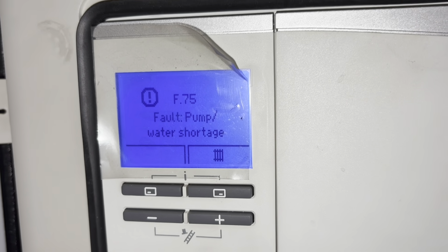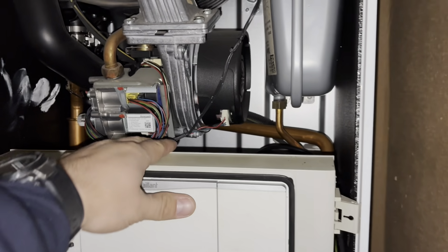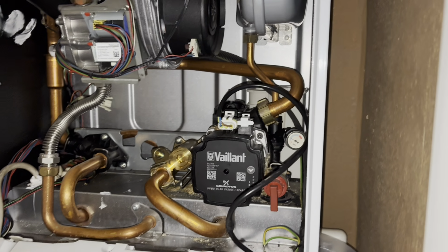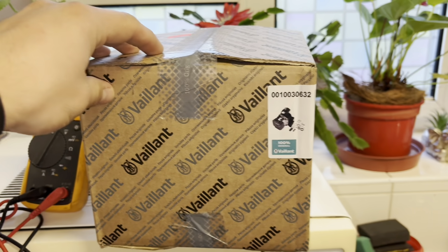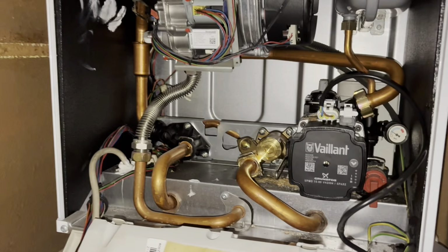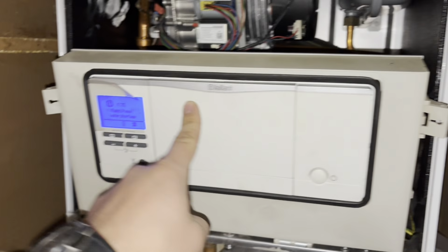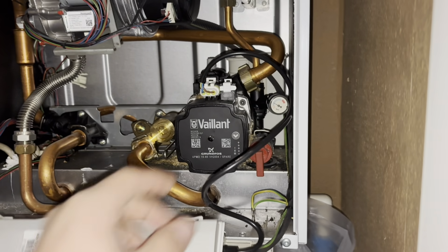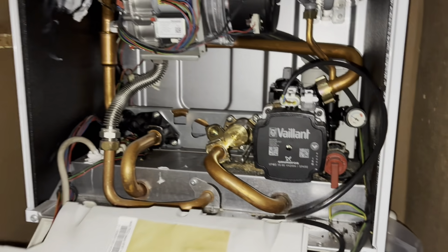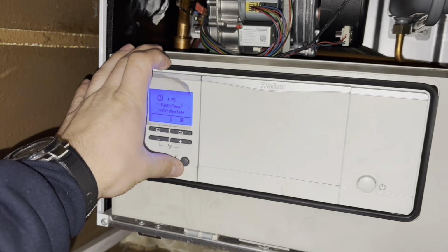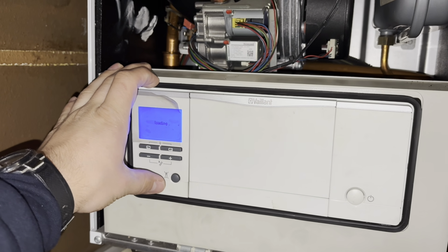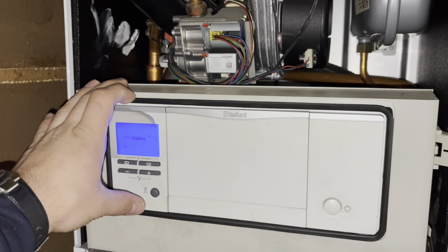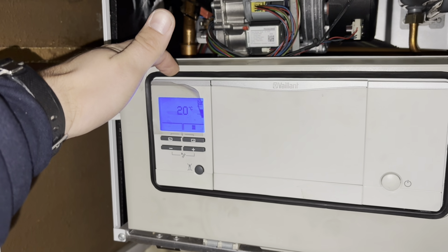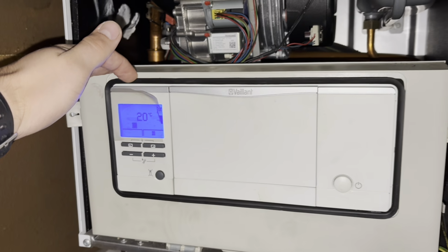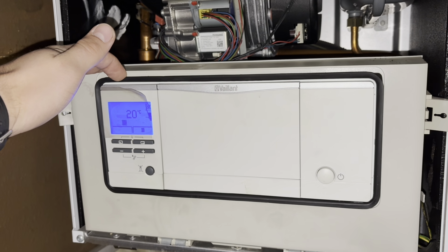Called out here to an F75. A new pump has been booked in by another engineer. I've got the pump here. But first, before we fit the pump, we have to make sure it is the pump. So what you'll do is, when you reset the boiler, I like to see what happens when you reset the boiler. You can kind of tell straight away what the issue is.